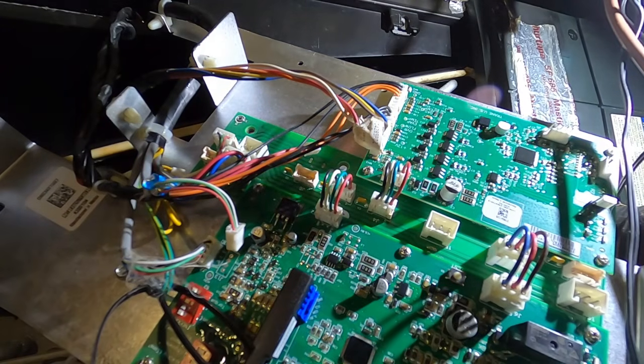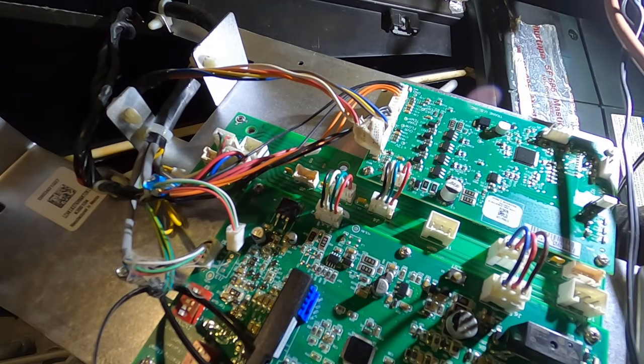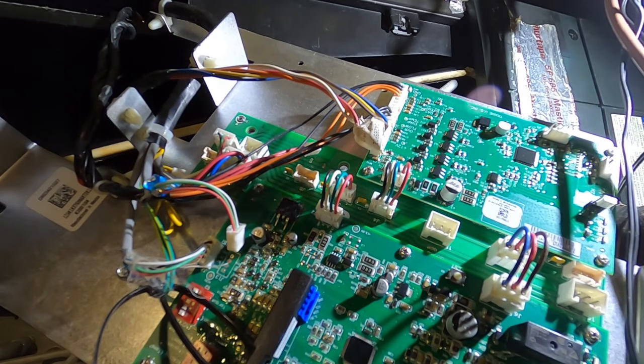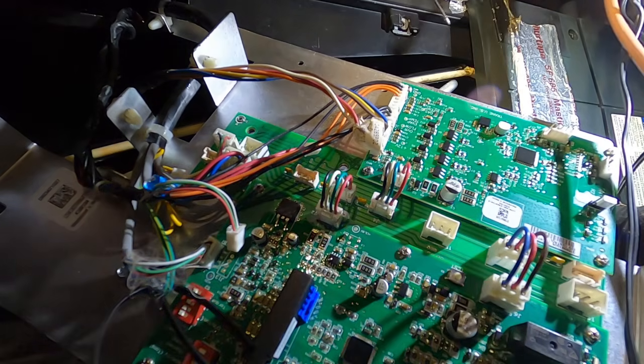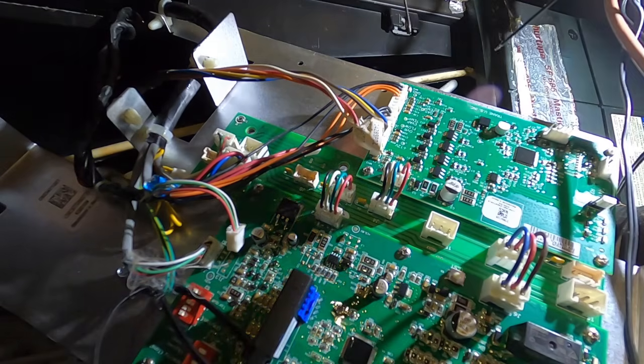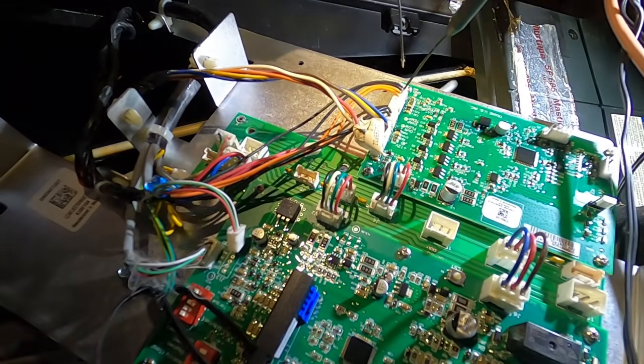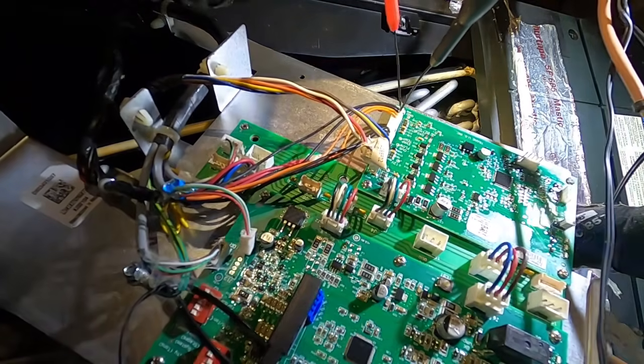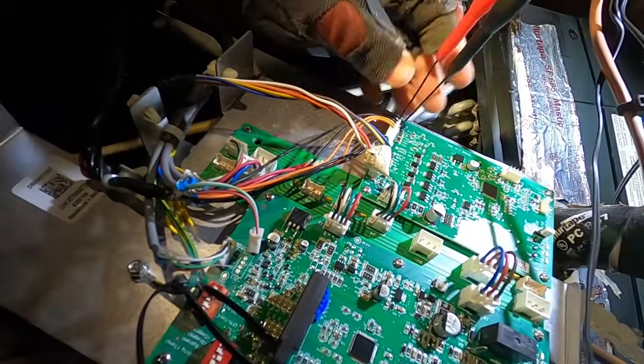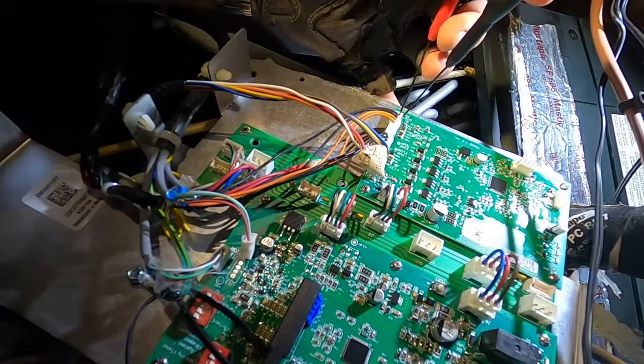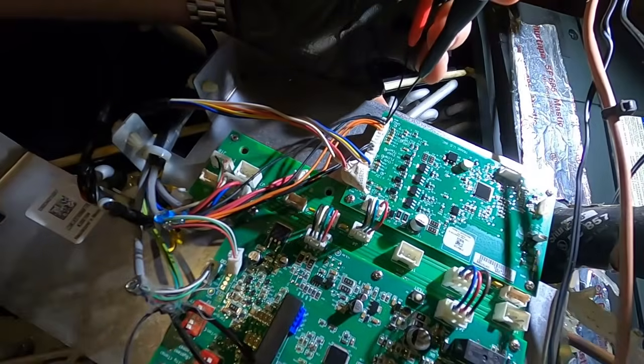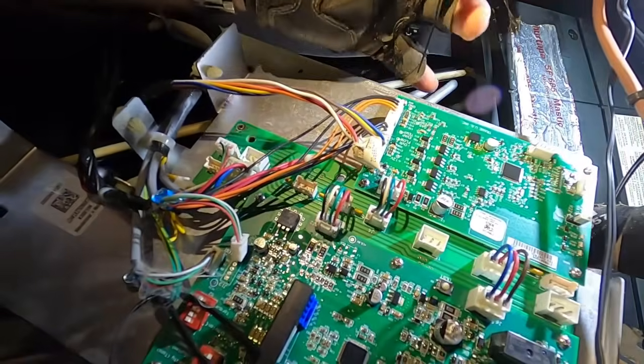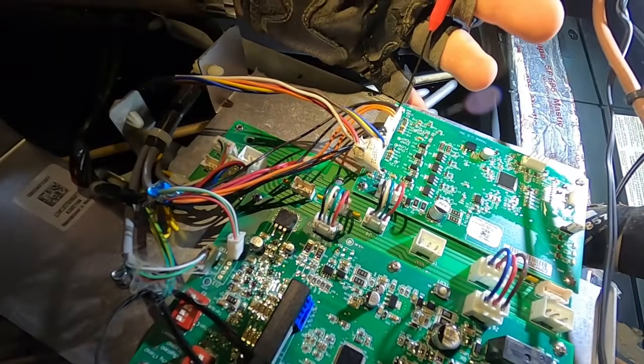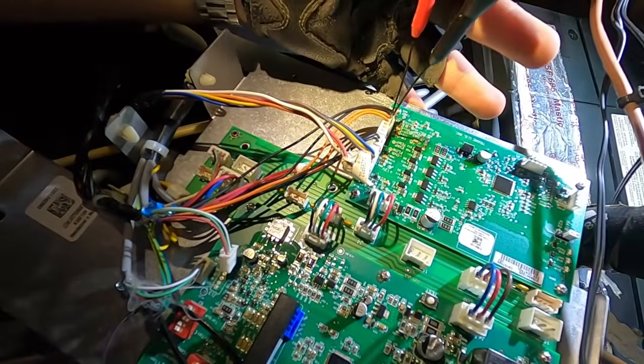So I am going to set this for DC voltage, and we'll do the black one first, which is going to be our gas sensor. And we got 1.6, which is right where it should be. About 72, 73 degrees in the house, roughly.